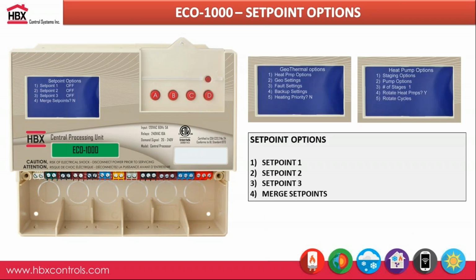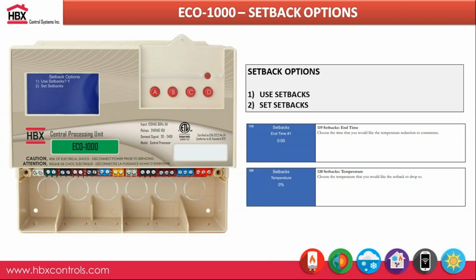Again, as I mentioned before, you have the option to incorporate up to 3 different set points. A big thing we always see is people doing domestic hot water from that, so you can put that as a set point option. But you may also want a set point to control maybe your pool or hot tub. Whatever you want to maintain at a set point, you have the option to do that using the EXP100. That set point option is always going to be the last relay, or the last EXP100 that you have attached within your system. That will be the relay operating those set points. You also have setback options as well.